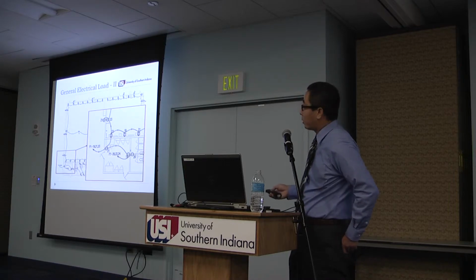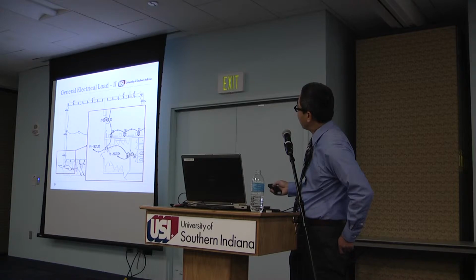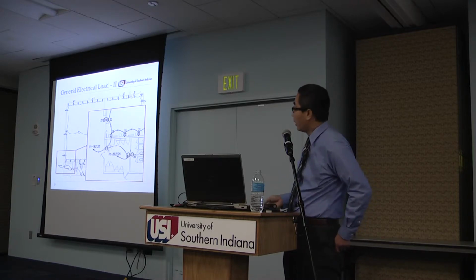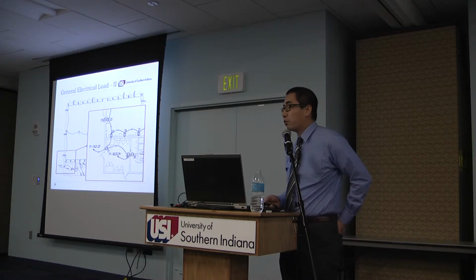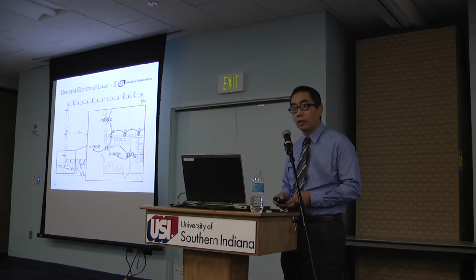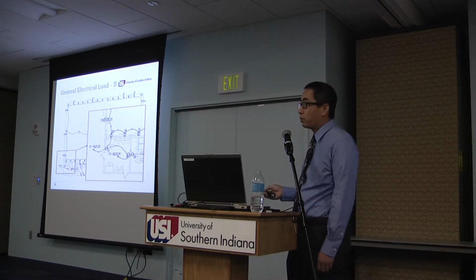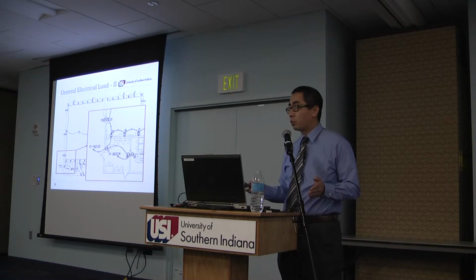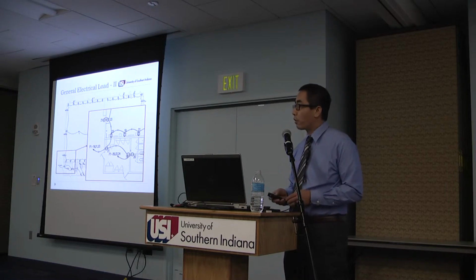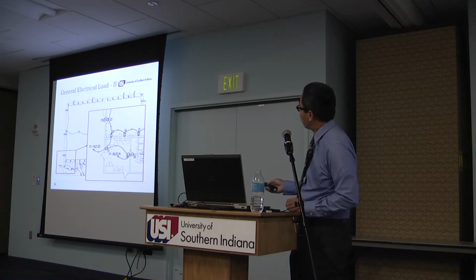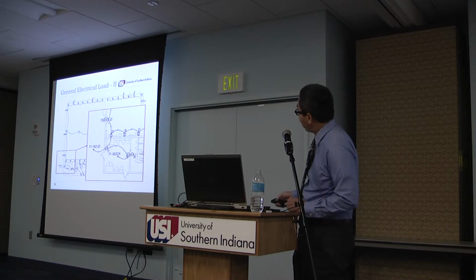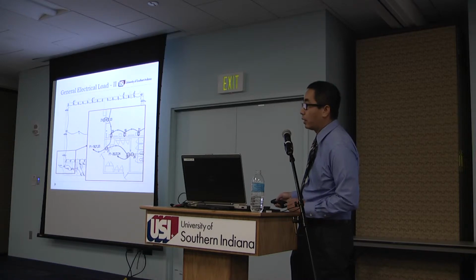And once we get the number tied down, we can lay out the receptacles around the perimeter of the shop. There's no code requirement for industrial and commercial buildings in terms of the distance between the receptacles. But there's the general requirement for residential buildings. If you look at a house, the space is maximum 12 feet on center. So we think it's a good rule of thumb to follow. That's how we lay out the receptacles here. There's the roll-up doors on both ends. That's why you see we skip that area, so we can't run a receptacle there. And so we tie all the receptacles together, and this is the enlarged picture of this portion here. So we tie them together, then this home run connects to the electrical panel.